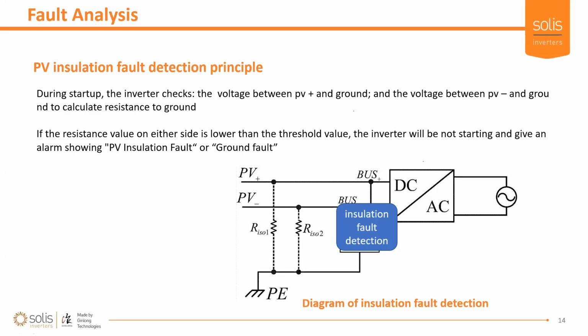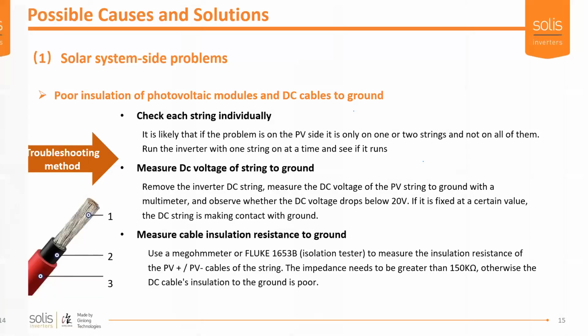Yeah, so before it closes its grid relays and starts generating, it does this whole check and makes sure that there's no weak connection. PV isolation faults are only a function of resistance, whereas your leakage current faults can be a function of capacitors too. Thank goodness I'm not doing my presentation on leakage current. It's quite a headache. It's an interesting fault to deal with. So yeah, maybe in the future.